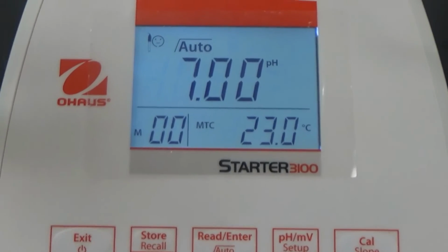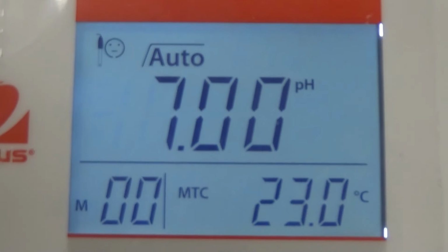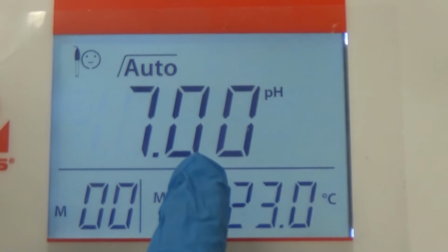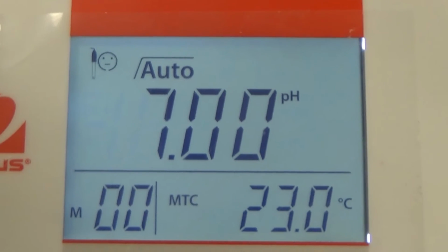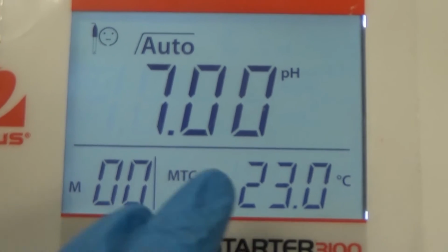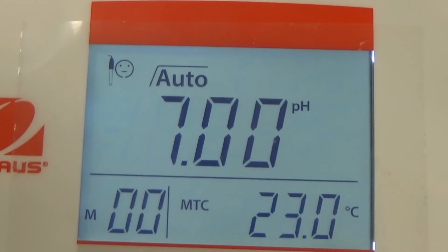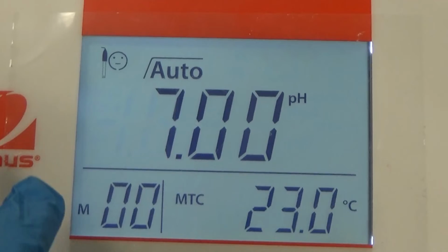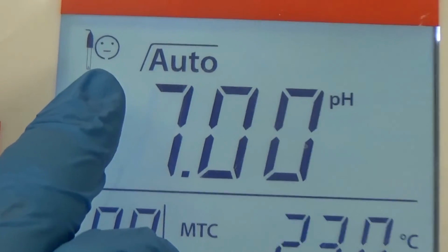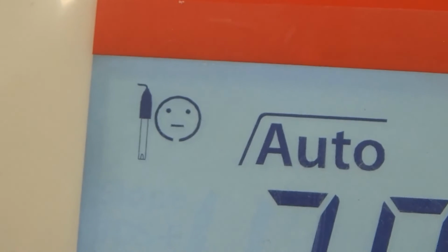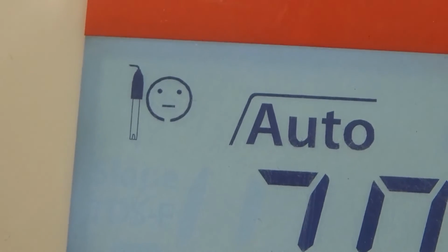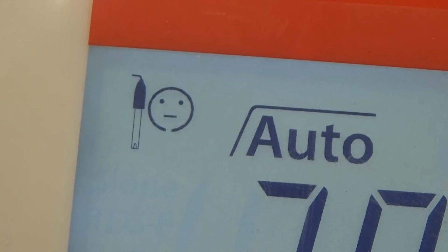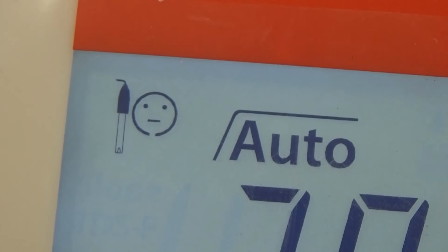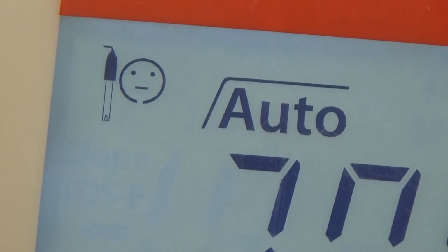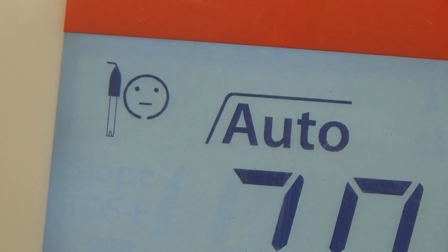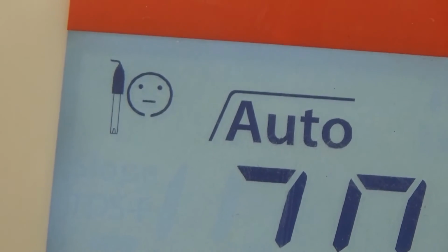Apart from the buttons, you will notice the screen itself has different numbers. So the upper one is the pH reading to 2 decimal places, and here's the temperature of the solution. But one of the more important parts to notice is on the upper left corner there's a smiley face with a probe image. So this will tell us if we had a good calibration or not. Right now it's kind of an in-between happy and sad face. This means that it is not calibrated. If it's a good calibration, it'll be a smiley face, and if it is a bad calibration, it'll be a sad face.